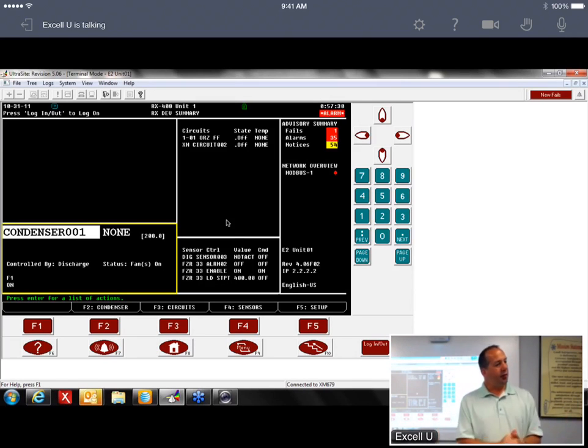If we have our network up and running, the E2 has default parameters for the device that will run a case circuit out of the box. I always like to take the E2 parameters and push them down into the device. That's why it's important to have that network up and running on a remodel so you can do that. You can rely on the hotkeys, but I think it's a lot easier to troubleshoot and tell what's going on if you're working from the E2.